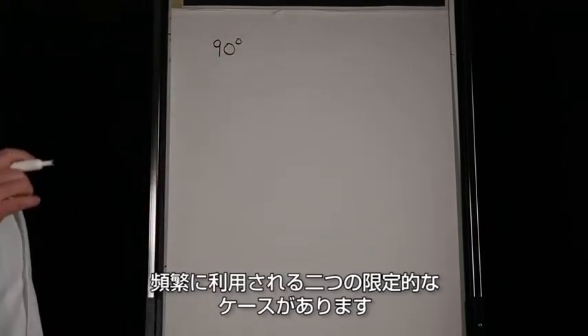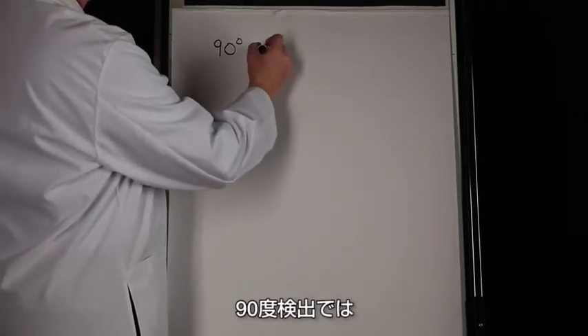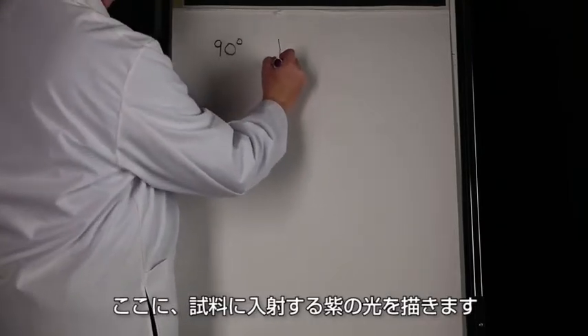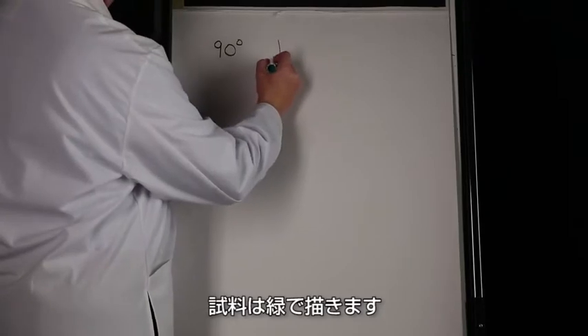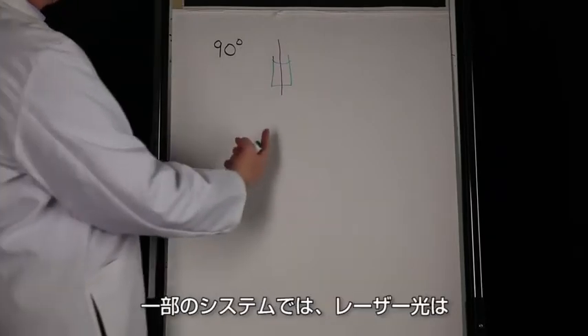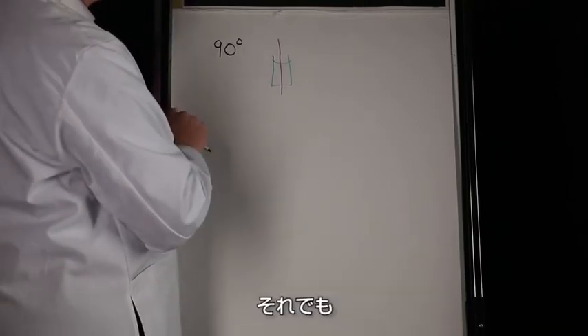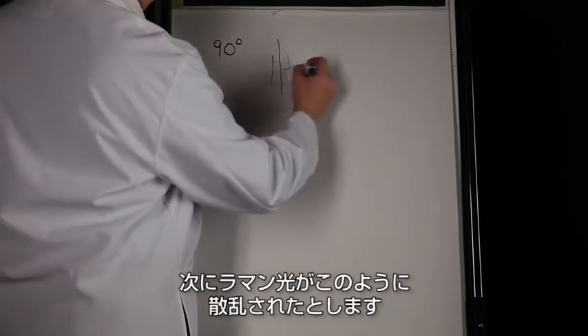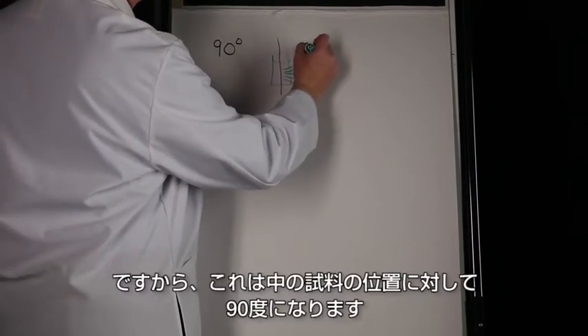One is 90-degree detection. In 90-degree detection, the laser beam enters the sample — I'm going to draw it here as a purple beam coming down into my sample, which I'll draw green again as a cuvette with liquid in it, just for simplicity. The laser beam comes in from the bottom in some of these systems, and then the Raman light is collected at 90 degrees relative to the sample.